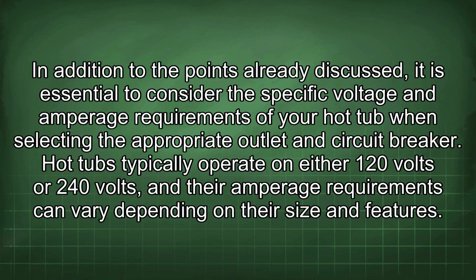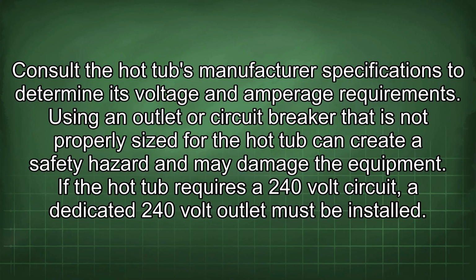In addition to the points already discussed, it is essential to consider the specific voltage and amperage requirements of your hot tub when selecting the appropriate outlet and circuit breaker. Hot tubs typically operate on either 120 volts or 240 volts, and their amperage requirements can vary depending on their size and features. Consult the hot tub's manufacturer specifications to determine its voltage and amperage requirements. Using an outlet or circuit breaker that is not properly sized for the hot tub can create a safety hazard and may damage the equipment.